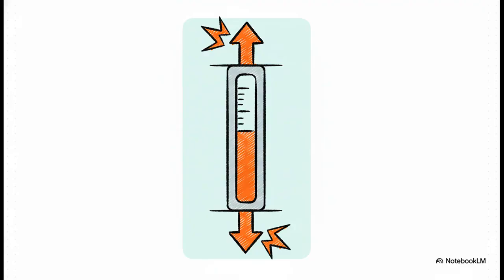And just to complete the picture, while our CTD has an underflow bit for going too low, its counterpart, the CTU, has an overflow bit, the .ov bit, for going too high. It's really that simple. Overflow is for counting up, past the max limit, and underflow is for counting down past the min limit, two sides of the exact same coin.